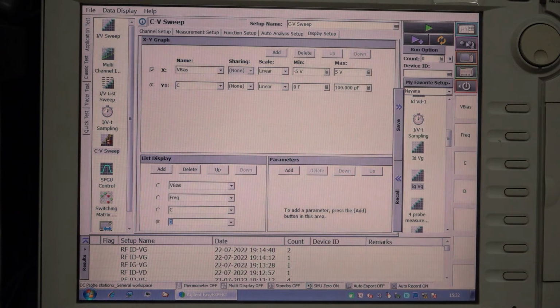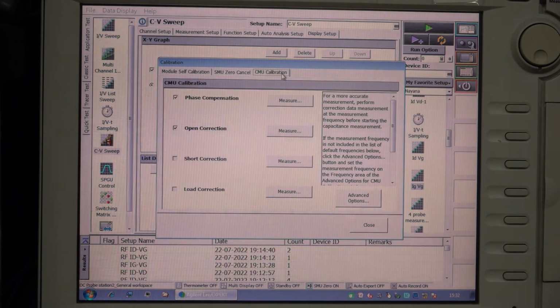Before going for the measurement, I need to calibrate this particular unit, which has 4 different types: phase compensation, open correction, short correction, and load correction. Currently we are not measuring any low-value device, so we can use only the open and phase compensation. If you use a very small value of device, say 1 pico or lower, we can go for a short correction. So currently I will be using phase compensation and open correction.